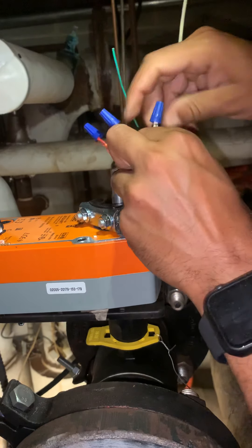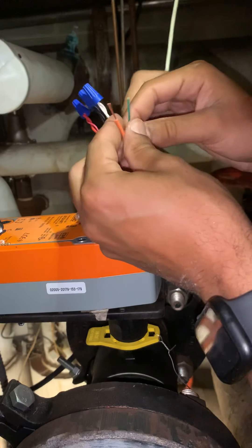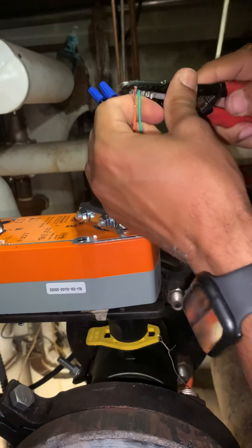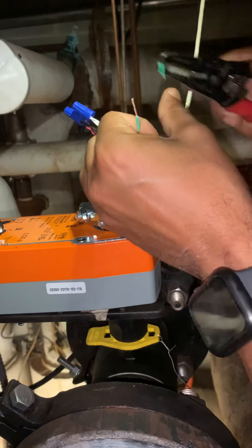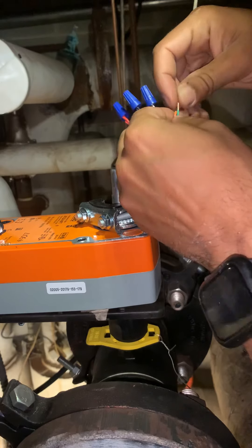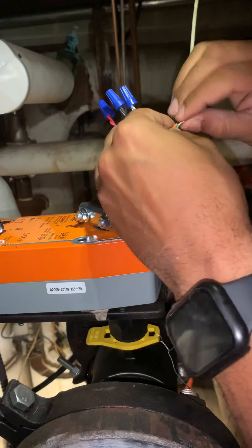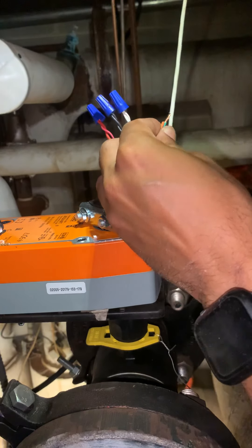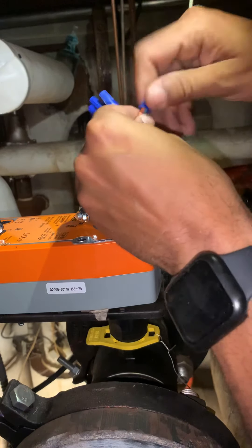Alright, so remember, this is my input signal to this actuator coming from the controller. Now, my green wire is going to be connected to my orange wire — it's going to be my output signal, feedback from this actuator. It's going to be connected to my controller and it's going to be an input to my DDC controller.